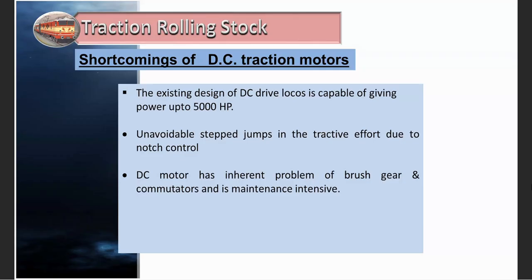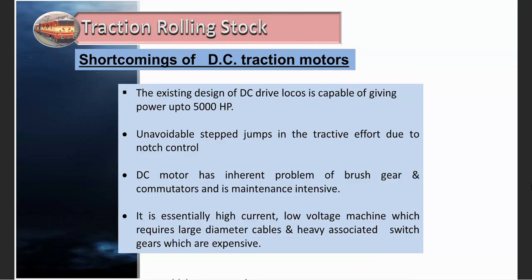The DC traction motor has the inherent problem of brush wear and commutator wear, and they are maintenance intensive. Essentially, DC motors are high current, low voltage machines because they operate at 750 volts. In order to have 5000 horsepower, the current requirement is very high. Whenever there is a higher current requirement, it means the cable size must be larger, making the cables heavy and expensive since more copper is used to manufacture them.